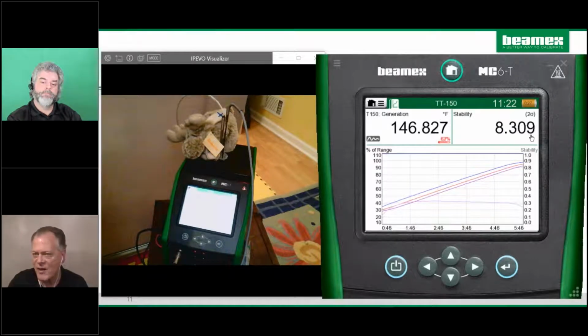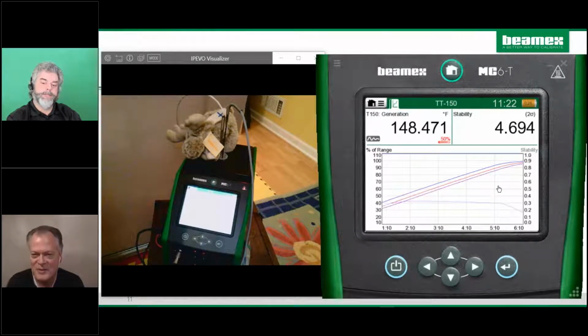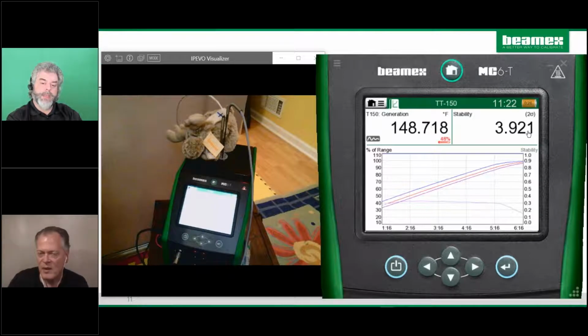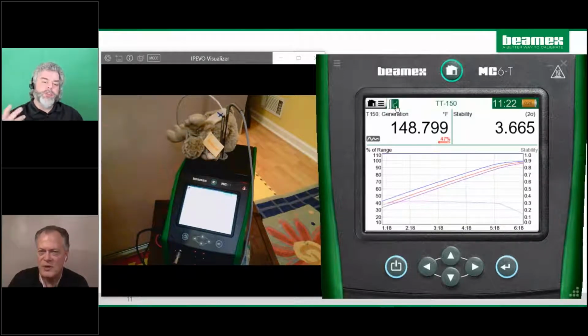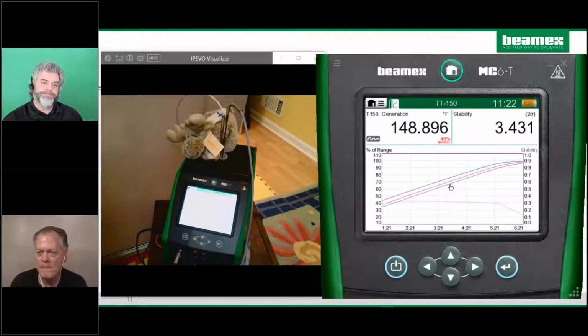So our stability graph is just showing a factor of 1, and it's showing that the transmitter is actually pretty stable, and that's because I have some dampening on it. I put, I think, 1 second of dampening on it, so it's not moving as fast as maybe the temperature probes are. But again, temperature is kind of a slow-moving parameter. Anyway, now you can see the stability starting to drop. And you can also look at it as a confidence level.